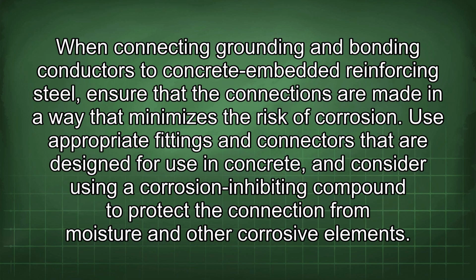When connecting grounding and bonding conductors to concrete embedded reinforcing steel, ensure that the connections are made in a way that minimizes the risk of corrosion. Use appropriate fittings and connectors that are designed for use in concrete, and consider using a corrosion-inhibiting compound to protect the connection from moisture and other corrosive elements.